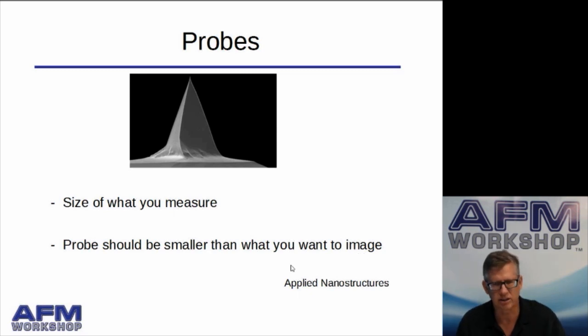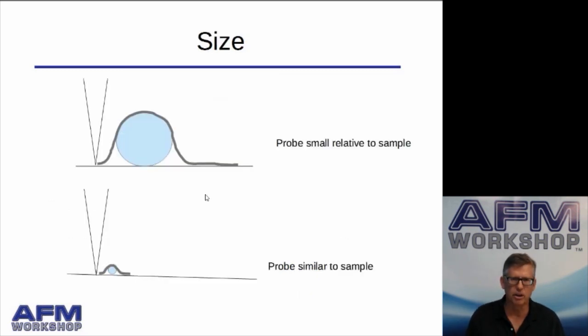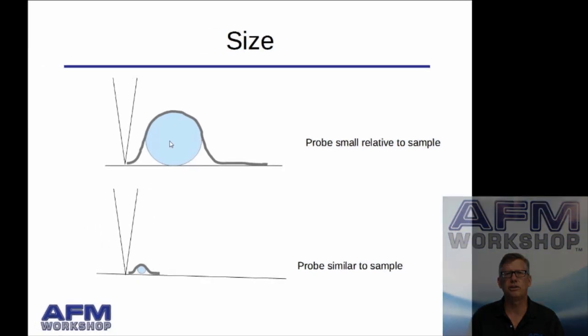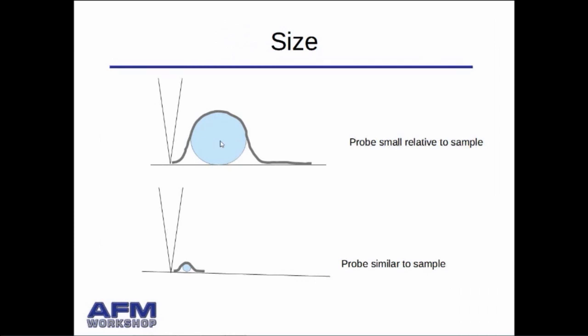I have here on the next slide the example of a probe going over a nanoparticle. And there are two things that you'll note here. The first is that no matter how sharp the probe is, you'll get the correct measurement for the height of the nanoparticle. And this is general for a lot of atomic force microscope measurements: when you're measuring heights, that's the vertical dimension, the probe geometry is not so important. However, if you're measuring the width, it's quite important.